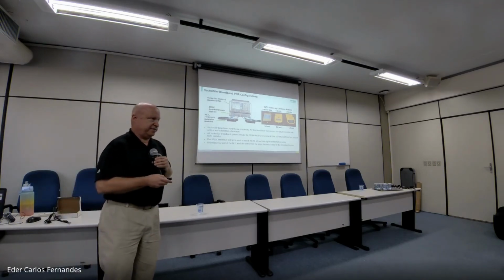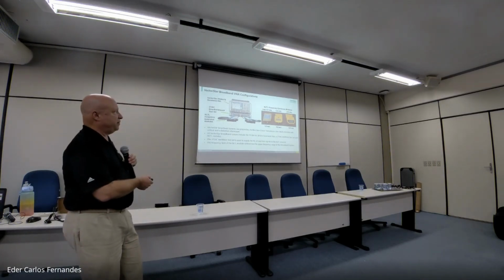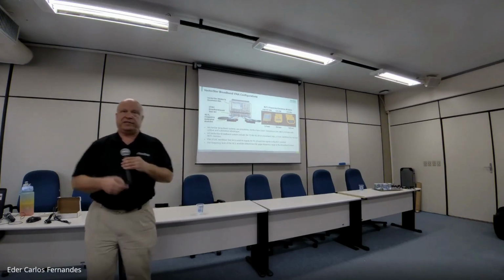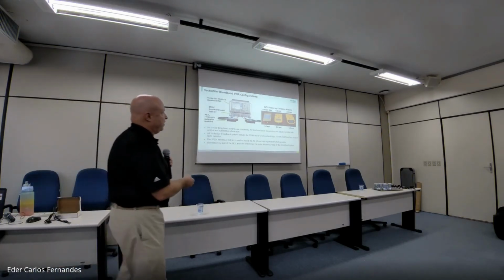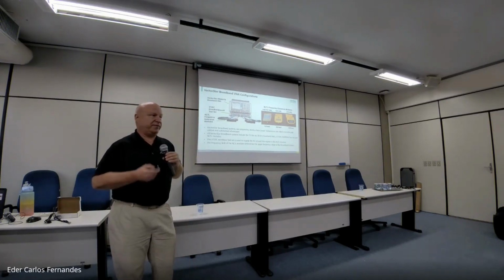So for the broadband system, currently we have 3 different bands, up to 125 gigahertz in 1 millimeter, up to 145 in 0.8, and up to 220 gigahertz in 0.6. Now you might look at those pictures and say, what's different between them? Well, the connector is different. 2 of the models have threaded connectors, which are kind of more traditional that we're used to. We have CalKits that are threaded, we can use with those.